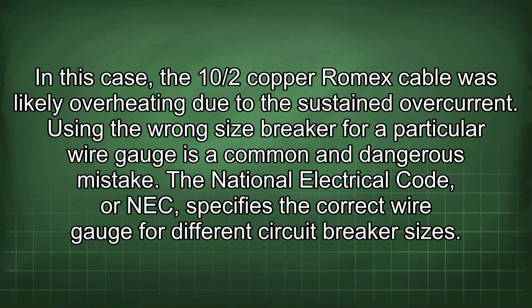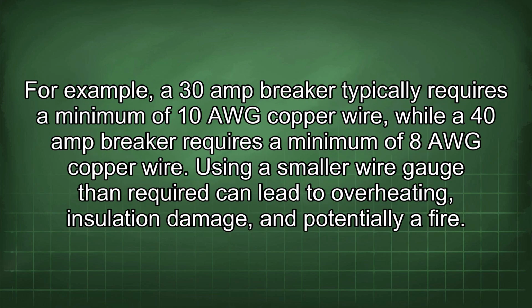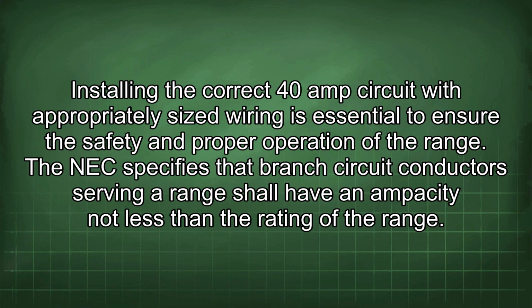The National Electrical Code, or NEC, specifies the correct wire gauge for different circuit breaker sizes. For example, a 30 amp breaker typically requires a minimum of 10 AWG copper wire, while a 40 amp breaker requires a minimum of 8 AWG copper wire. Using a smaller wire gauge than required can lead to overheating, insulation damage, and potentially a fire. Installing the correct 40 amp circuit with appropriately sized wiring is essential to ensure the safety and proper operation of the range.